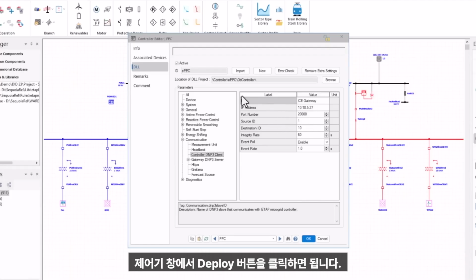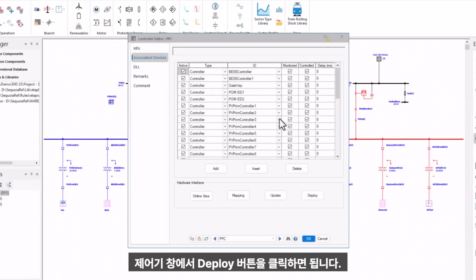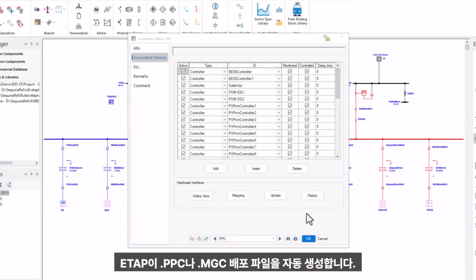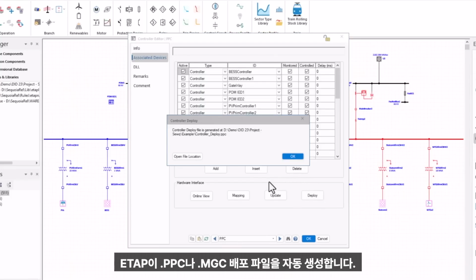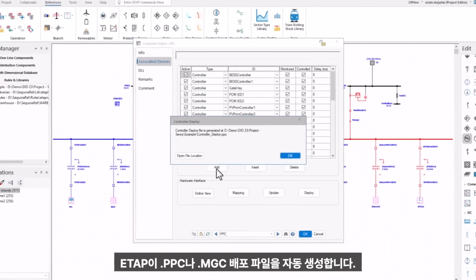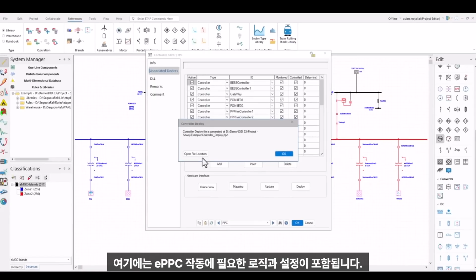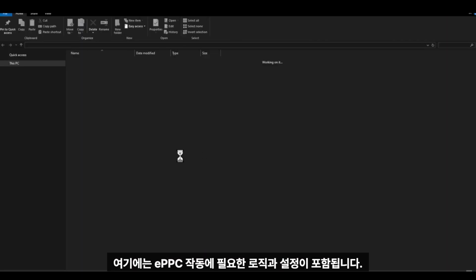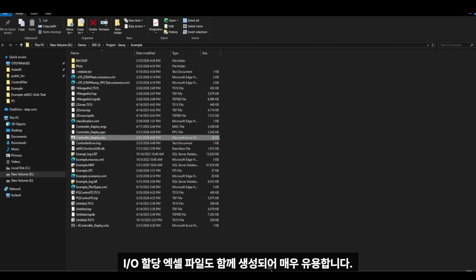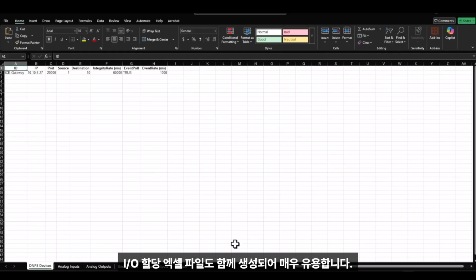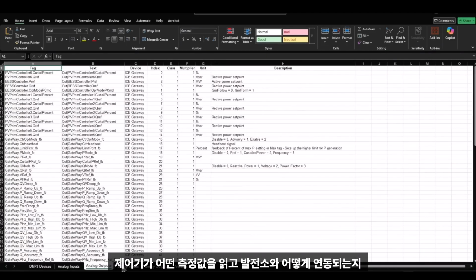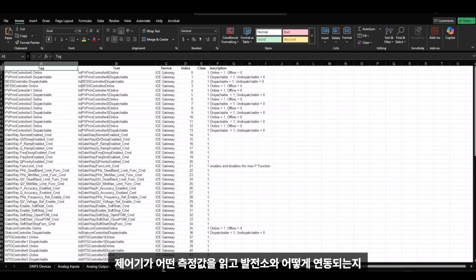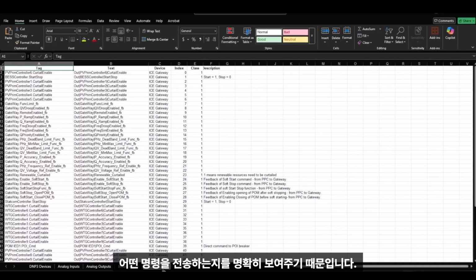This is done from the associated devices page by clicking the deploy button. ETAP then automatically generates a deployment file with a .ePPC or .mgc extension. This file contains the control logic and configuration needed for the ePPC to run properly. At the same time, ETAP also generates an Excel file listing the I/O assignments. This file is very useful because it clearly shows how the controller will interact with the plant, including what measurements it reads and what commands it sends.